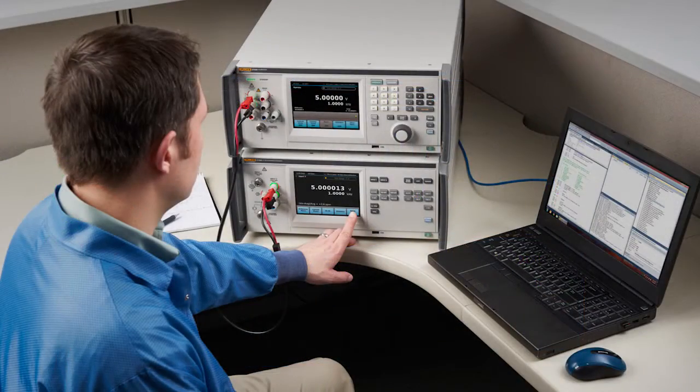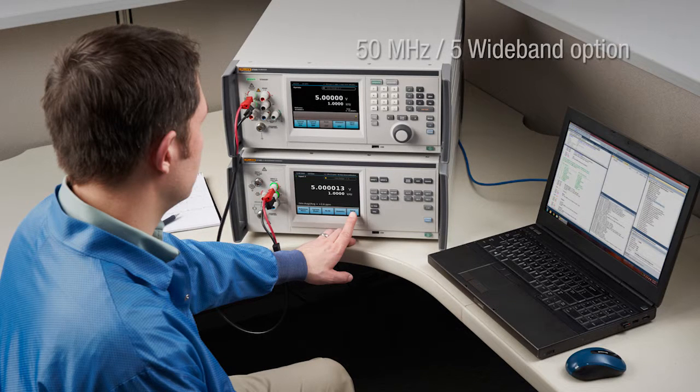The fourth major improvement is the addition of the 50MHz wideband option that extends the bandwidth to 10Hz to 50MHz for calibrating precise RF power sources.